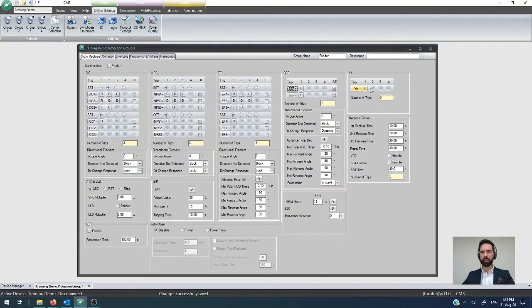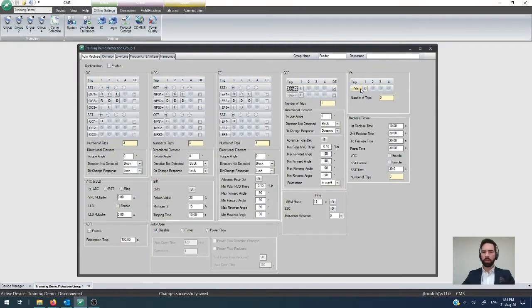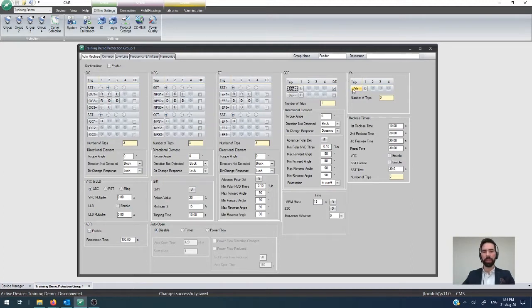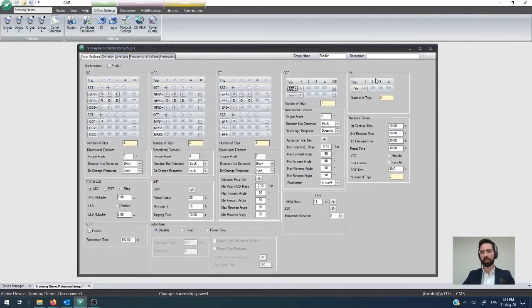The last element on this page that we haven't covered off yet is neutral admittance. Neutral admittance is a calculation that takes both the neutral current and the neutral voltage and divides one by the other. That gives you a polarized value based on conductance in the resistive plane and susceptance in the capacitive or reactive plane.